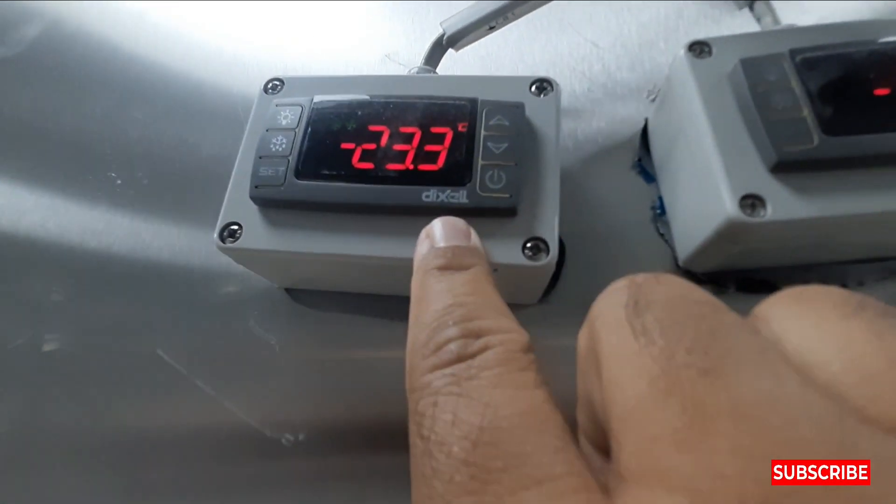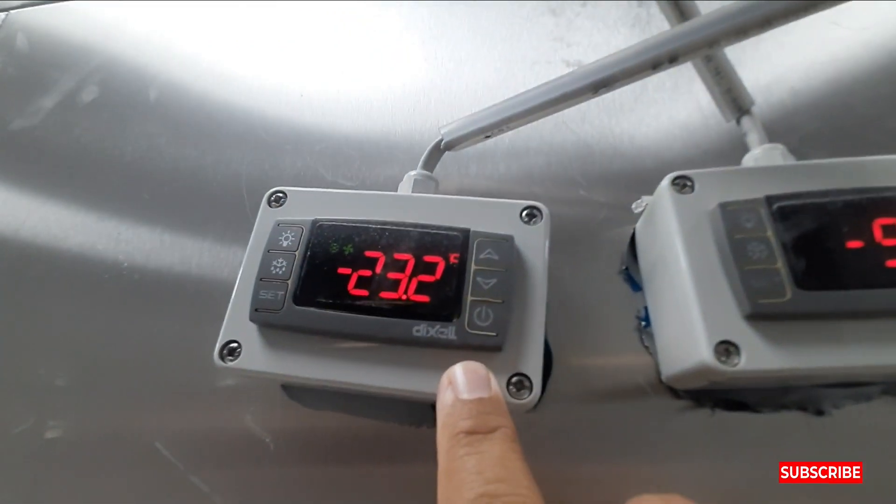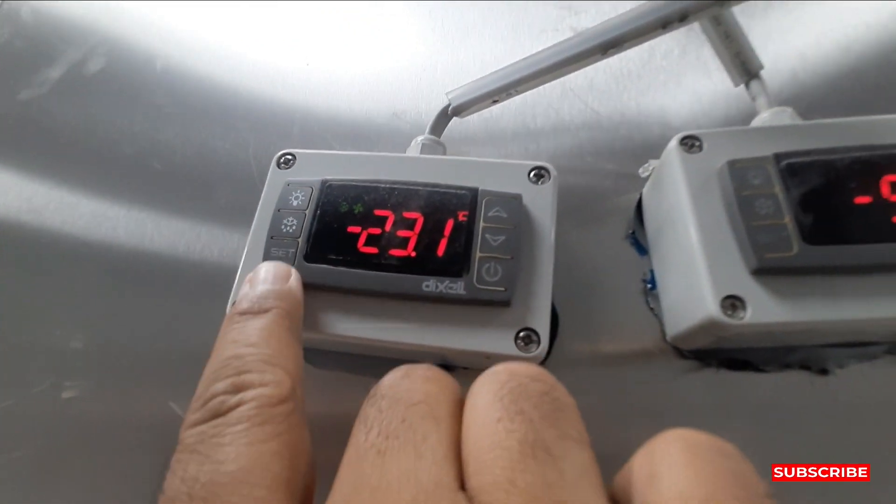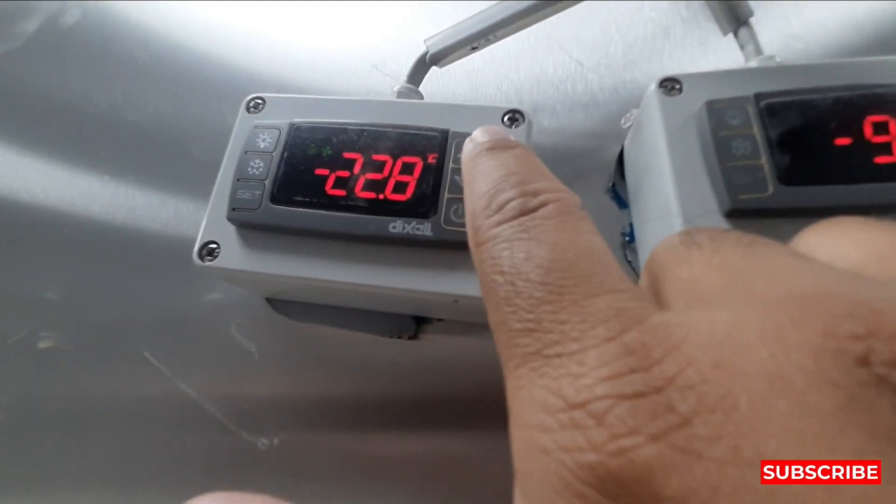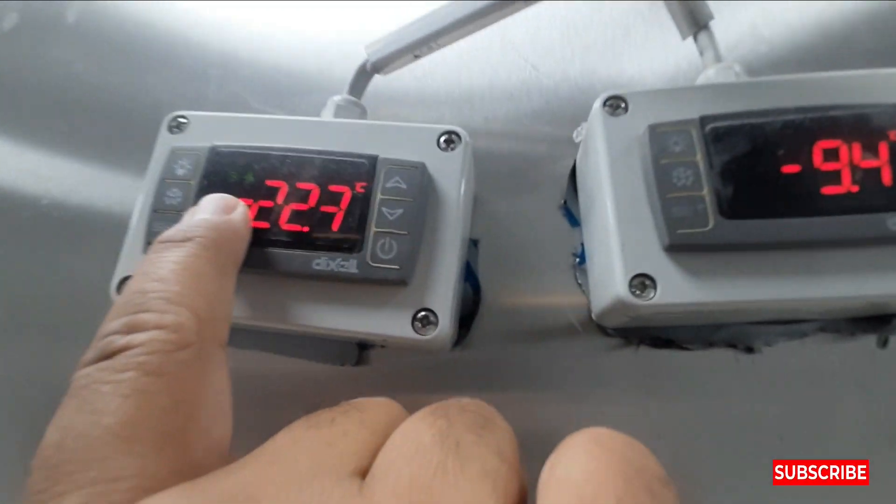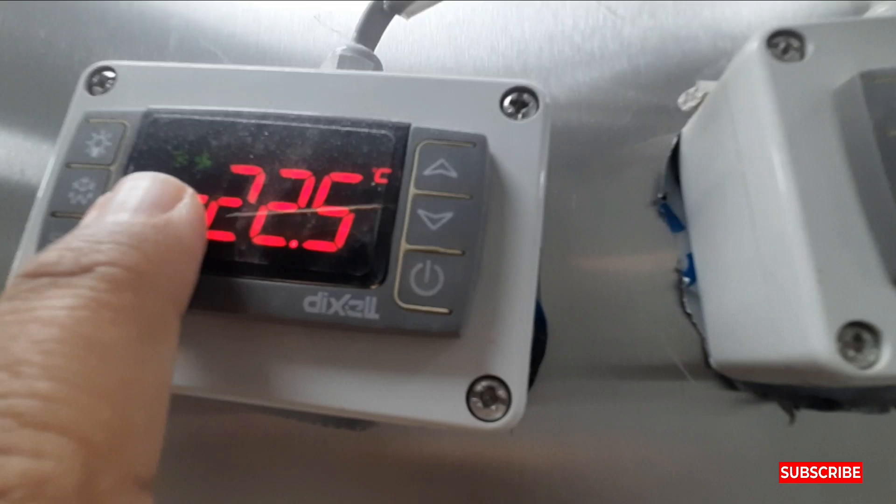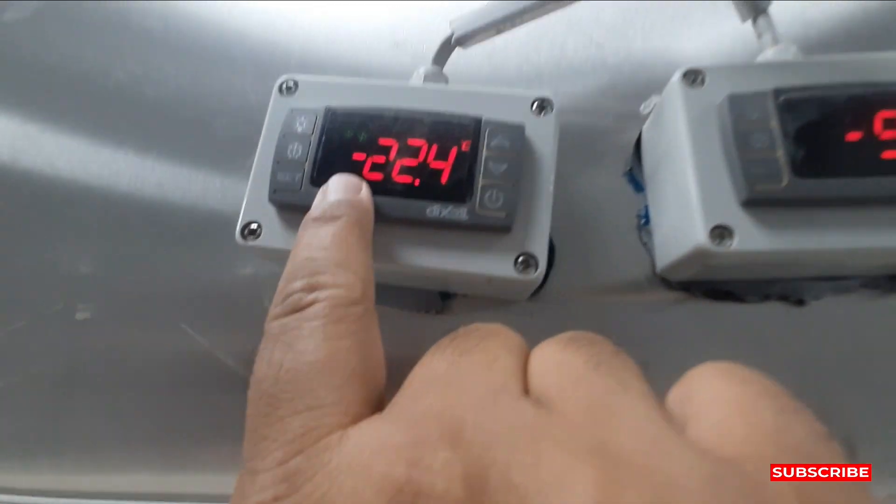This is the Dixell digital temperature meter we are using. You can see the temperature is going minus 22 because ice came inside on the evaporator coil. When ice comes on the evaporator coil, we need to defrost it.